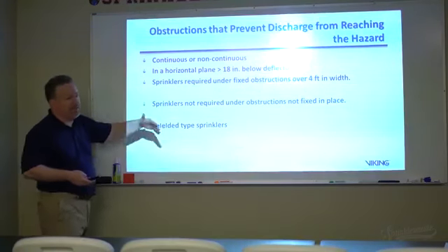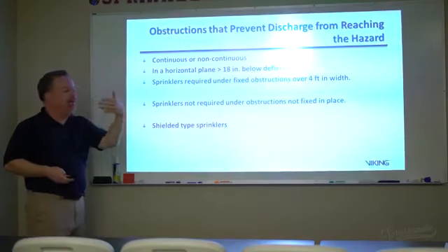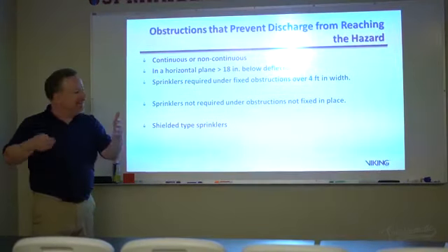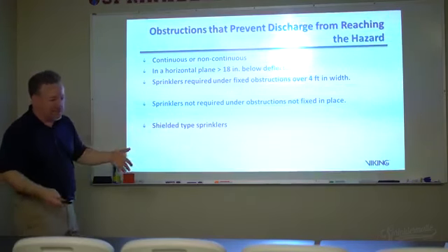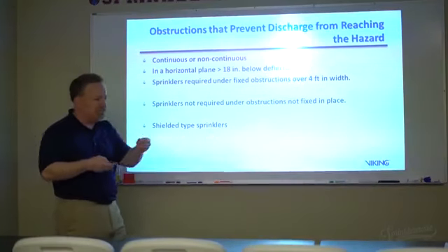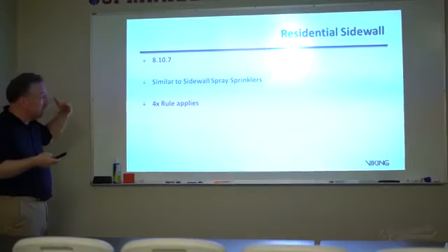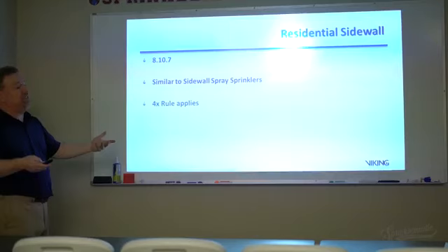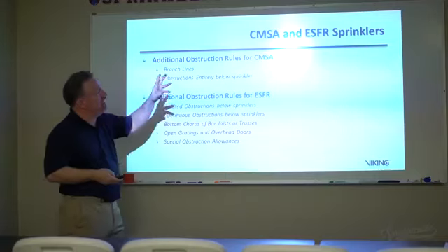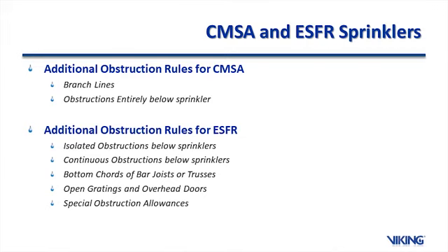Okay, so as you're moving down, once you've established the standard spray and the standard sidewall sprinklers, everything else simply follows that same specific pattern. Nothing really changes except the numbers, the distances. Residential sidewall looks a lot like sidewall sprays, and a lot like extended coverage sidewall spray sprinklers. The 4 times rule applies.